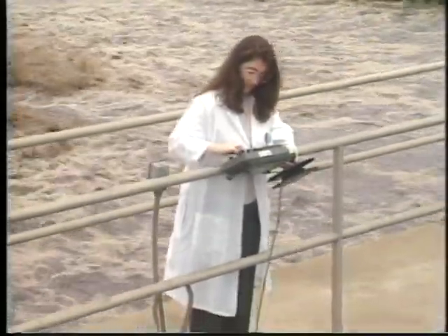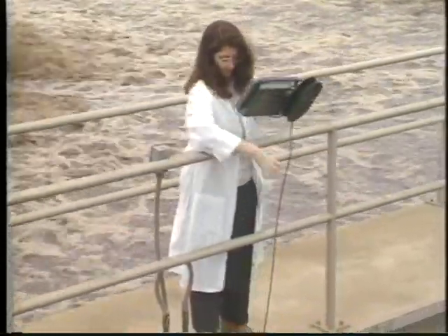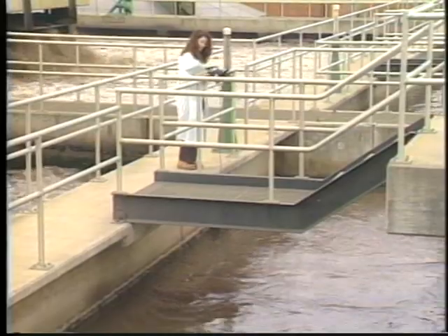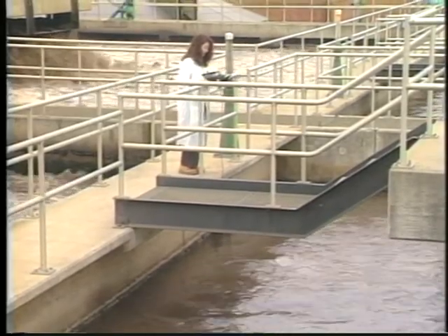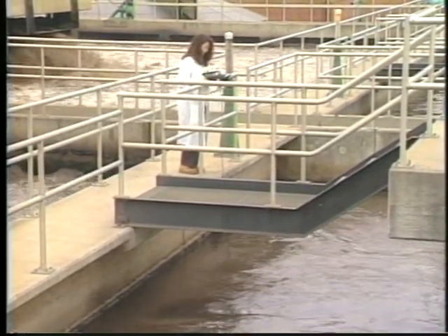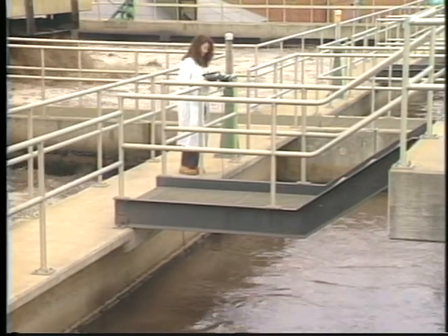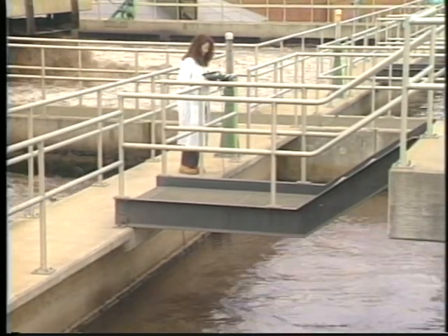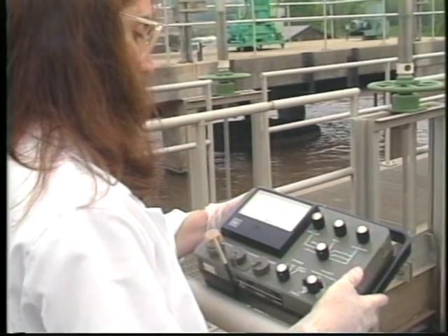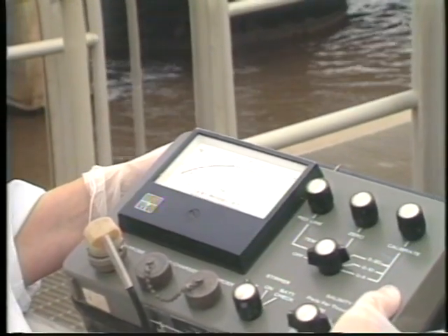One of the most important tests in an activated sludge treatment facility is the dissolved oxygen test. When checking DO levels, you should do a profile of the entire aeration tank. Generally, it is good to maintain a dissolved oxygen concentration of 2.0 mg per liter throughout the aeration tank. Low DO levels can lead to the formation of filamentous bacteria that cause the sludge to settle poorly. If the DO becomes depleted in the aeration tank, the contents of the aeration tank will become septic.